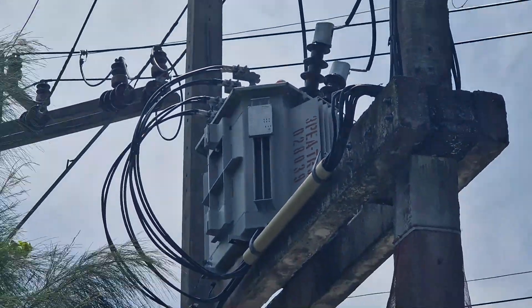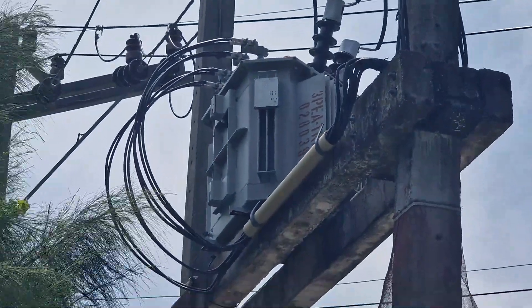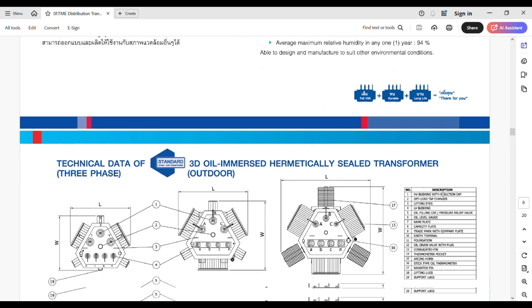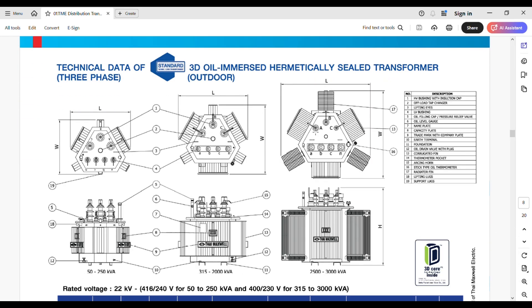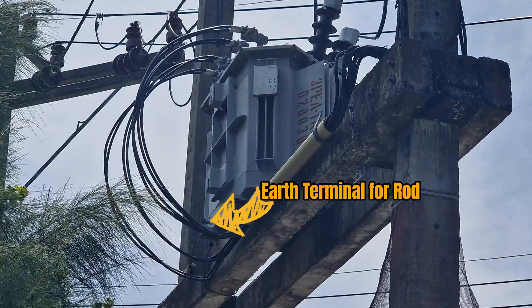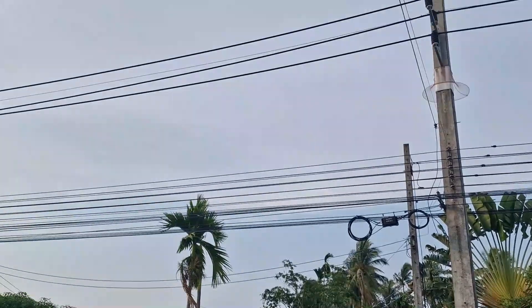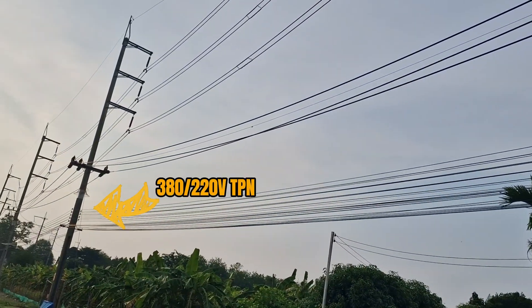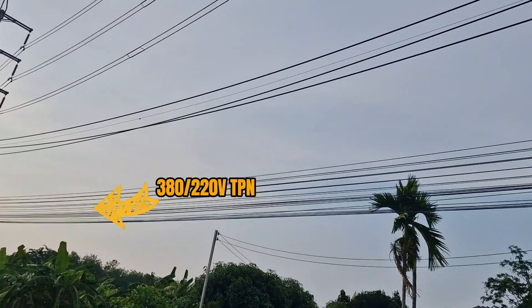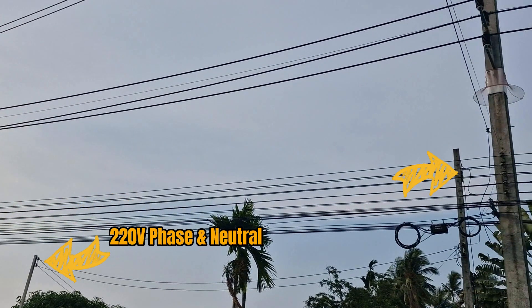It's why the delta winding is on the HV side and star is on the LV side. The neutral on the transformer LV side has the star point connected to Earth, with a rod shoved into the ground. It doesn't look like an Earth cable is provided to the consumers by the DNO, because who needs proper earthing when you've got hope and an Earth rod? So this explains the lower four cables — three phases and a neutral running along the street, with a phase and neutral branch going to each household on these lower pylons.